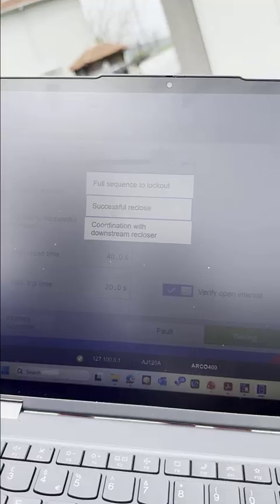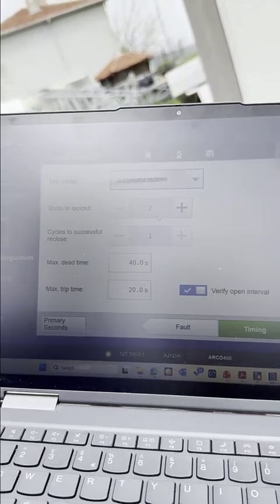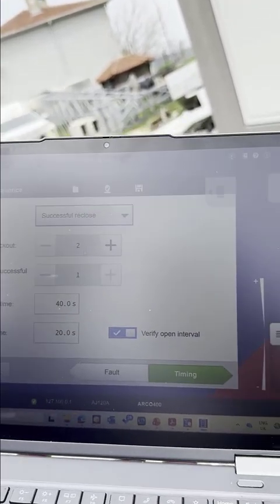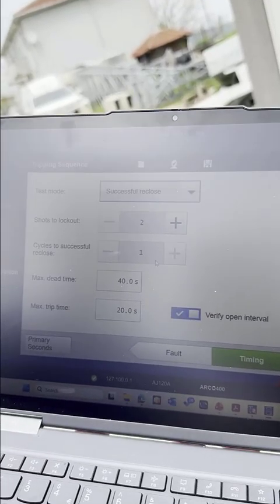You can select successful reclose or full sequence to lockout or coordination with the downstream recloser. Now we will test the successful reclose. So here the shots to lockout is 2, because we have only one shot. So the cycles to successful reclose will be 1.